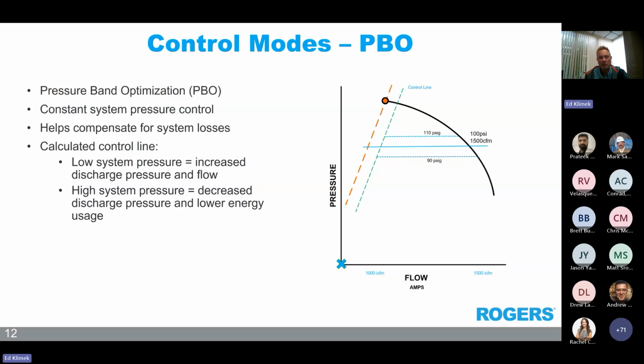As you can see here, before I start the animation, you have the 110 PSI is your above design pressure band set point. Well, the 90 PSI is your below design pressure band set point. The control line would be established during commissioning by completing surge testing at each of the 3 pressure set points to ensure maximum turn down across all the pressure bands. So you would do a discharge surge test, you would do a suction surge test to get your above and below set points.